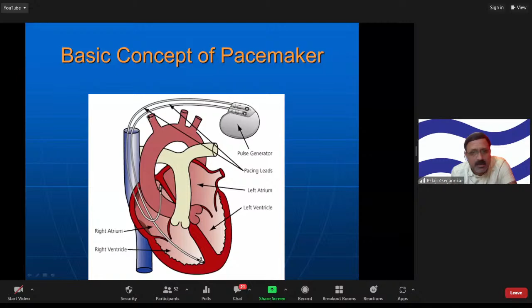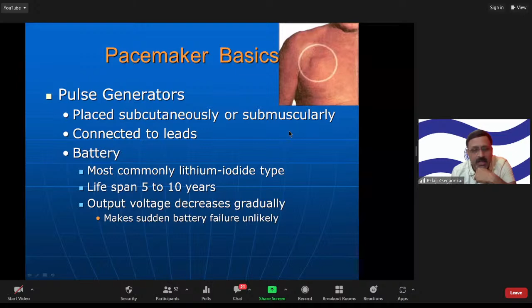Now, as I already stated, this is the pulse generator. These are the wires and these are the electrodes. And this is how it is placed, invariably subcutaneously, below the skin or below the muscle. It is connected to the leads. The pulse generator has a lithium iodide battery, which usually lasts 5 to 10 years. Over time the output voltage gradually decreases, but sudden battery failure is very unlikely in any pacemaker. This electronic circuit determines the function of the pacemaker itself.